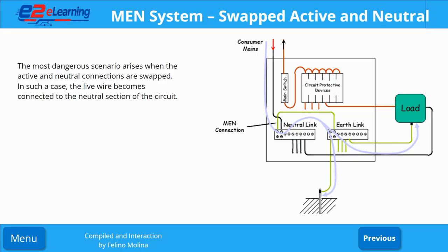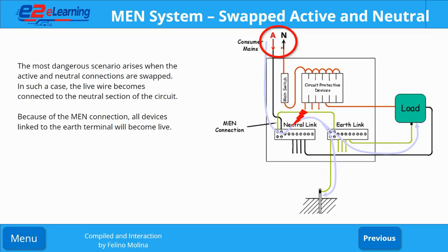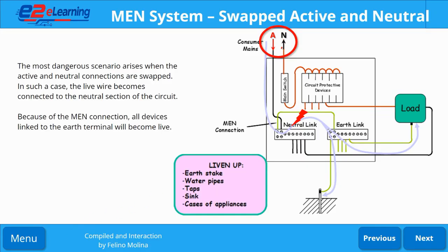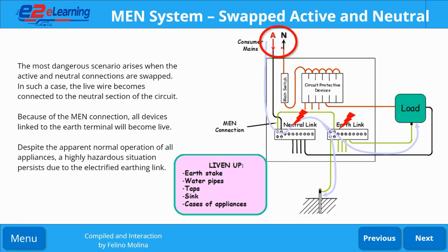The most dangerous scenario arises when the active and neutral connections are swapped. In such a case, the live wire becomes connected to the neutral section of the circuit. Because of the MEN connection, all devices linked to the earth terminal will become live. Despite the apparent normal operation of all appliances, a highly hazardous situation persists due to the electrified earthing link.